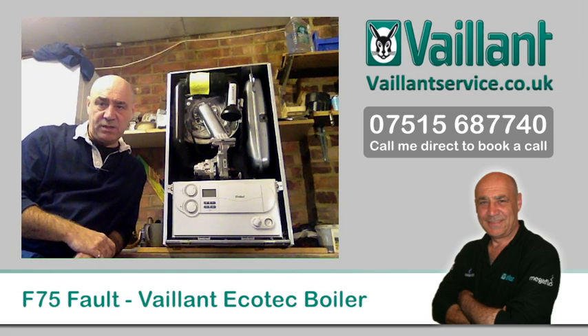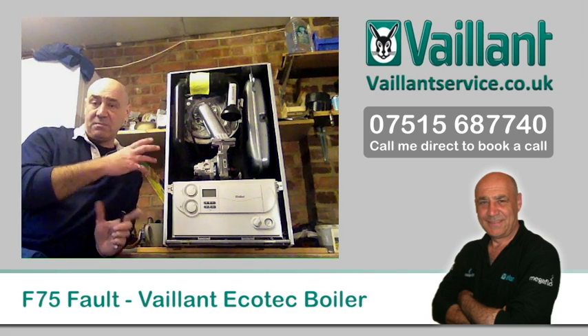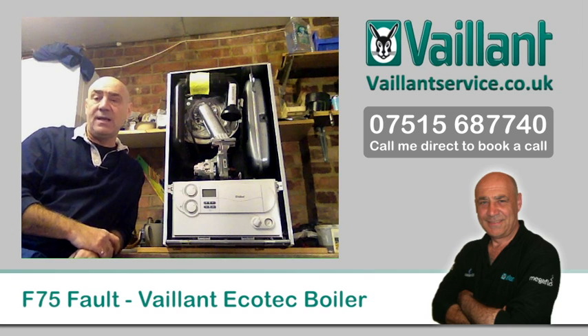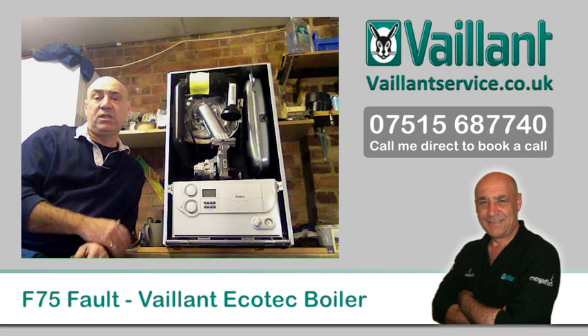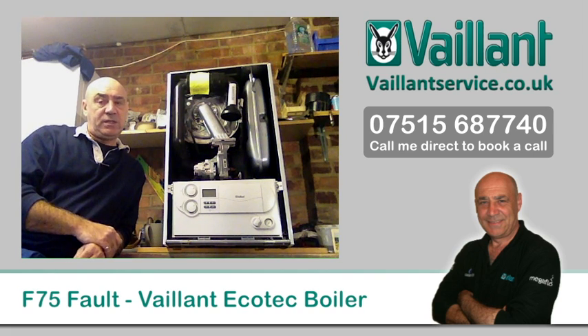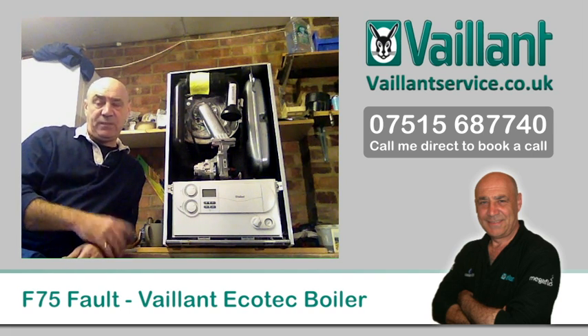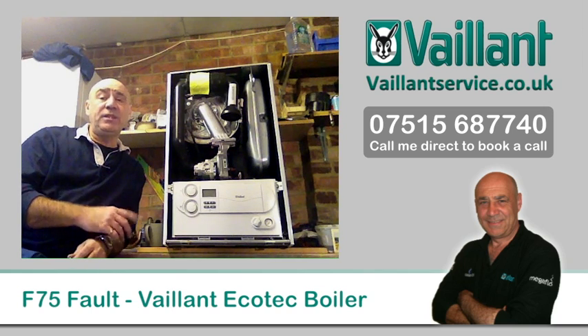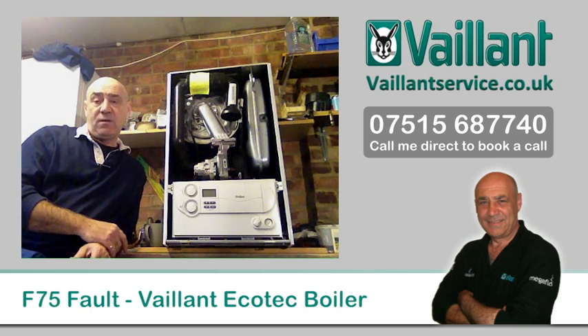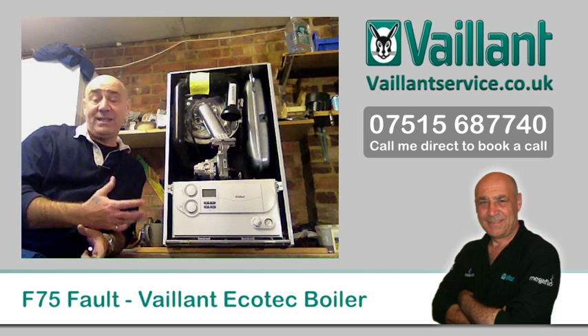On some occasions, if the main heat exchanger is badly blocked, then you might as well write off the boiler and go and get yourself a replacement. However, if it's not the heat exchanger, there are multiple reasons for the F75 fault code. First of all, we need to understand what the F75 fault code is and what it's trying to tell you.